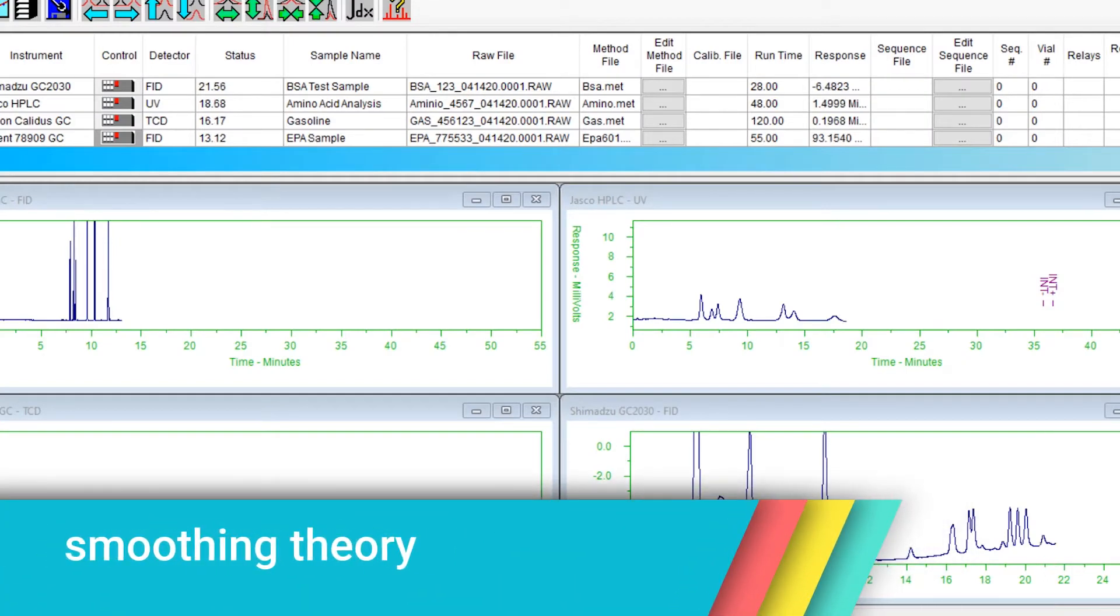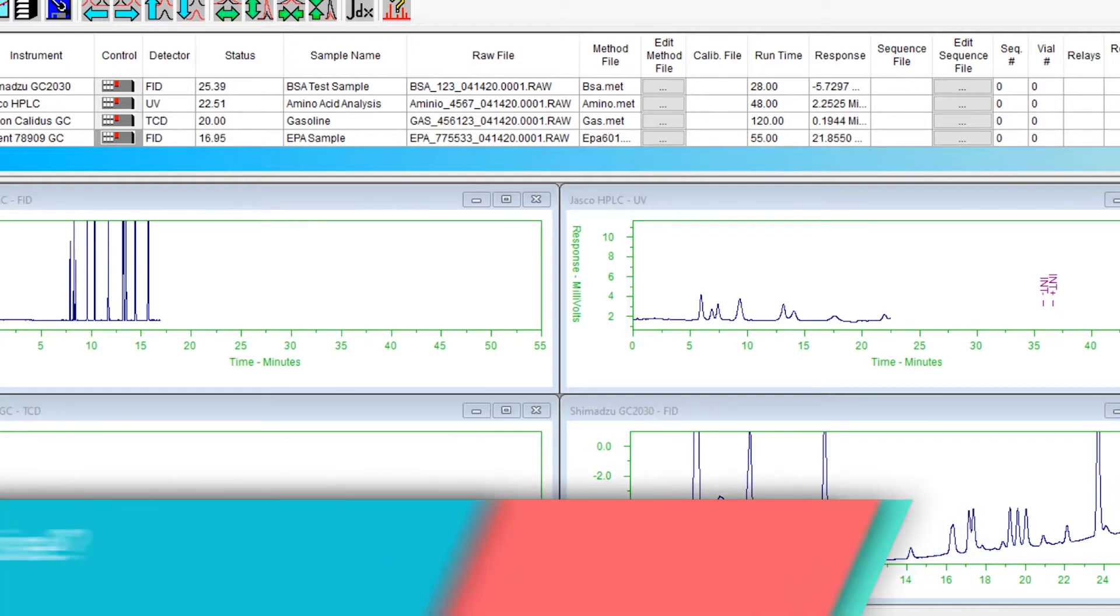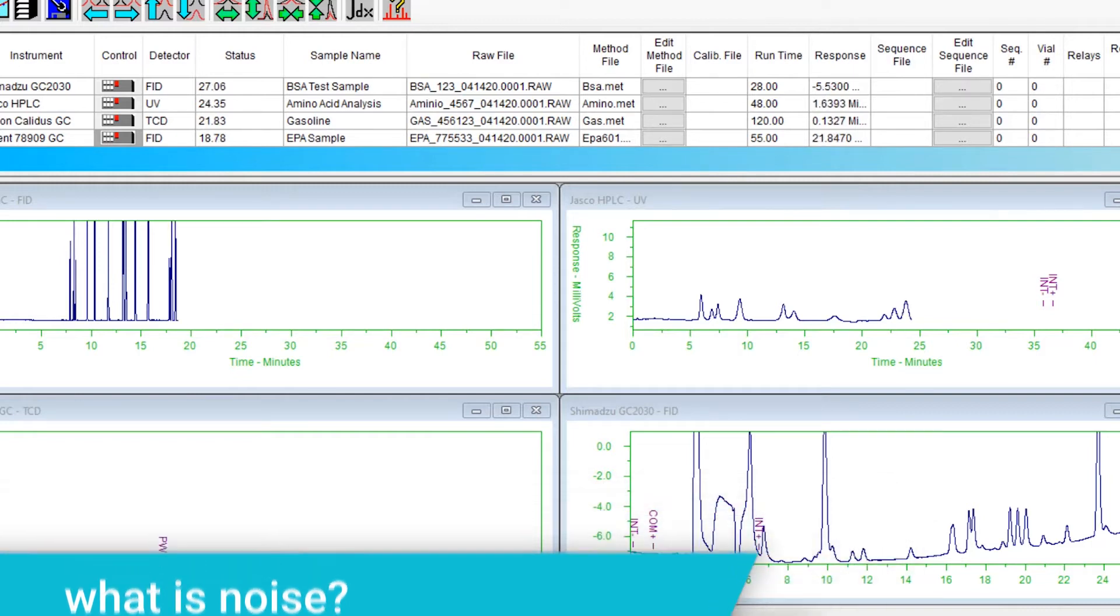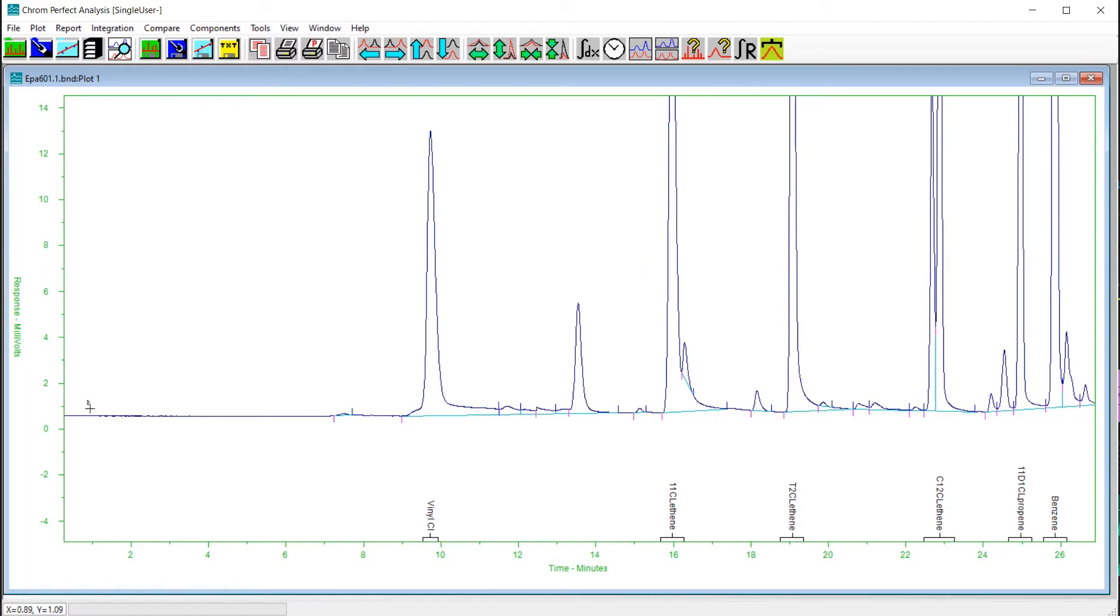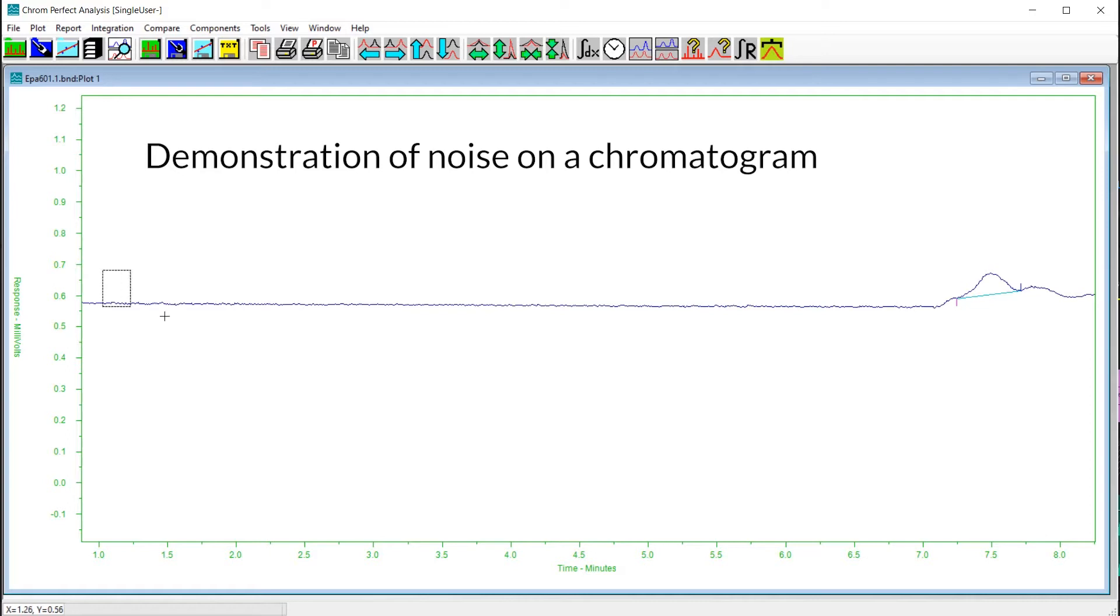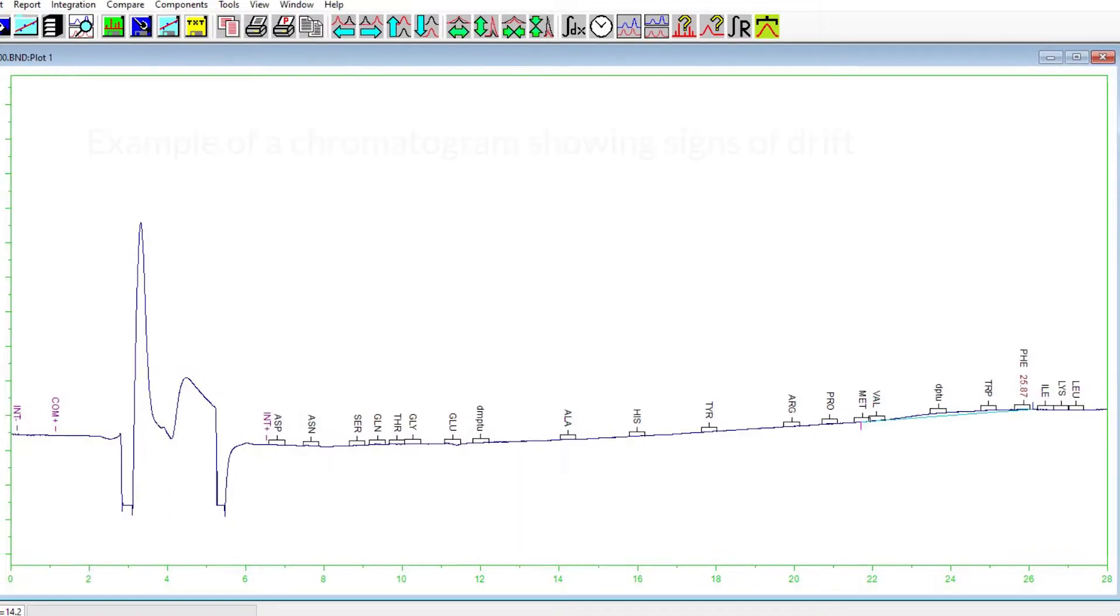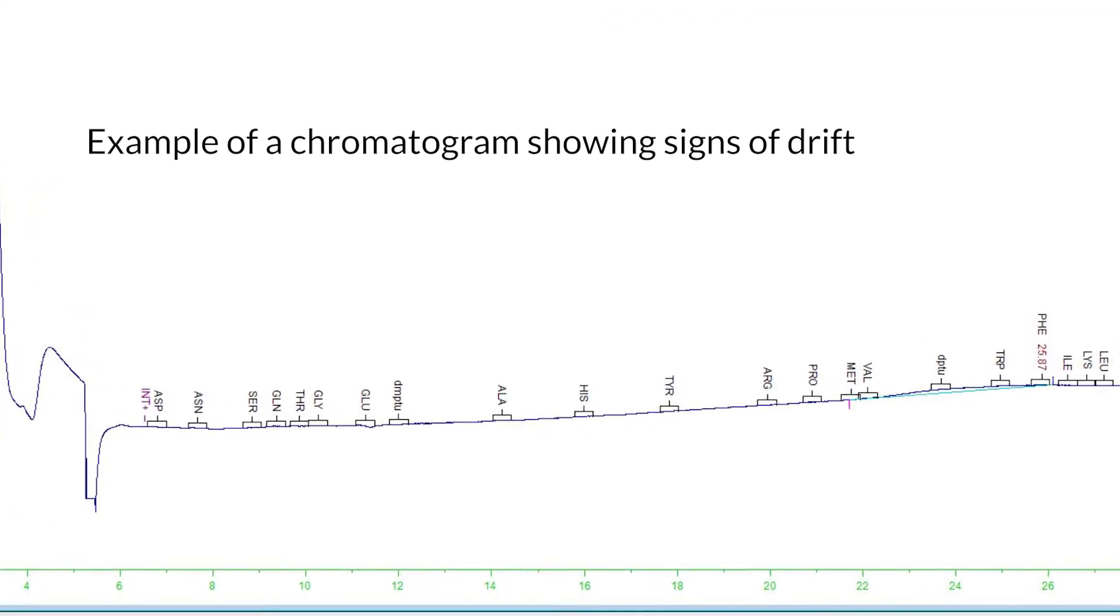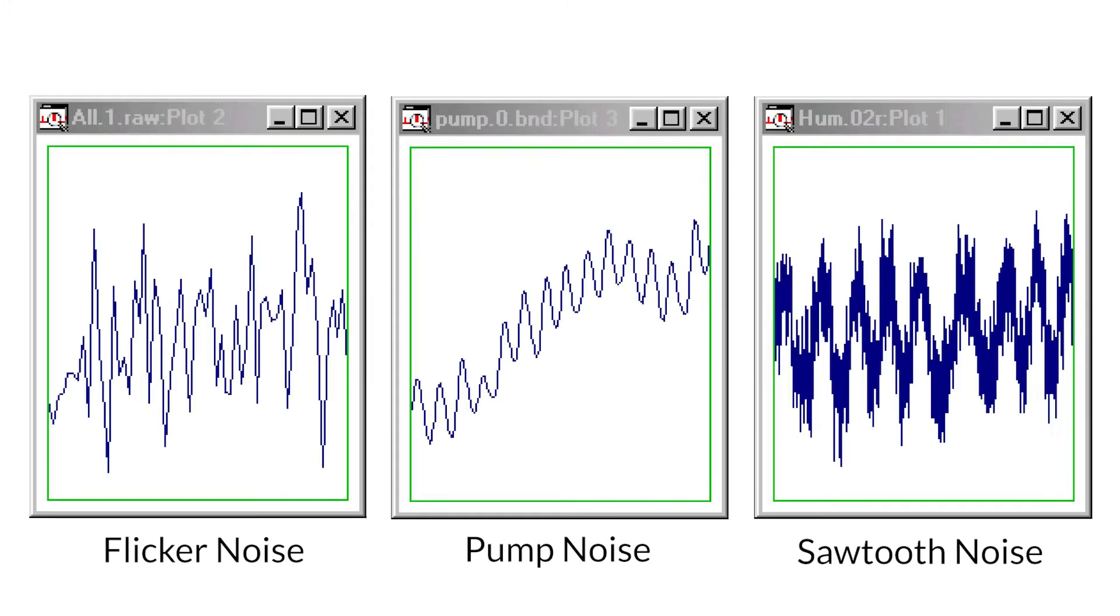Smoothing theory. This chapter explains the effects of detector noise on peak detection and quantification and how these effects may be reduced or eliminated by smoothing the chromatogram prior to integration. What is noise? Strictly speaking, noise is defined as any variation in the chromatogram that is not caused by the passage of an analyte through the detector. However, it is convenient to distinguish between slow fluctuations that occur on a time scale larger than the peak width (drift) and rapid fluctuations that occur on a time scale smaller than the peak width (noise). Smoothing reduces only the noise. To remove drift one must subtract a baseline chromatogram.